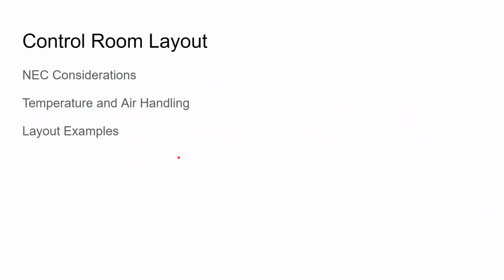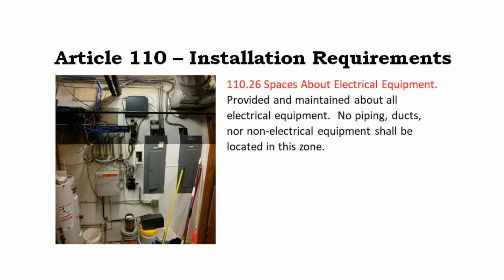Let's talk through some control room layout issues when you're designing your battery room, some stuff you need to be aware of. A common design error is that electrical equipment needs dedicated space and dedicated working space, meaning it can't share its space with water lines, gas lines, or even air conditioning ducts. Code requires electrical equipment to have its own space.